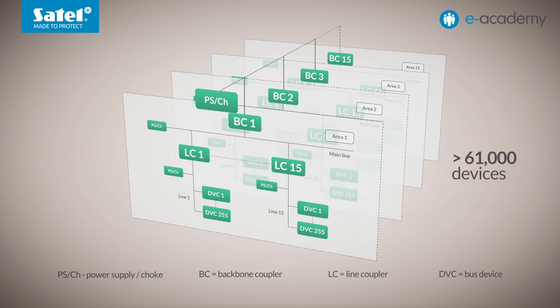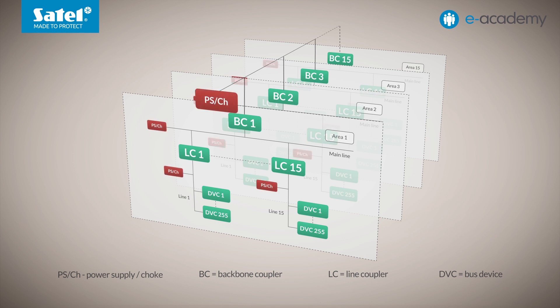It is worth adding that such a topology has several advantages. Firstly, the couplers provide galvanic isolation between areas and lines, which protects them in the event of an over-voltage, for example. In addition, all lines, including backbone and main lines for individual areas, have their own power supply. Consequently, the failure of one power supply unit will not cause the entire network to stop working. The rest of the system will continue to operate without interruption, excluding those functions that were carried out in the idle part of the installation.